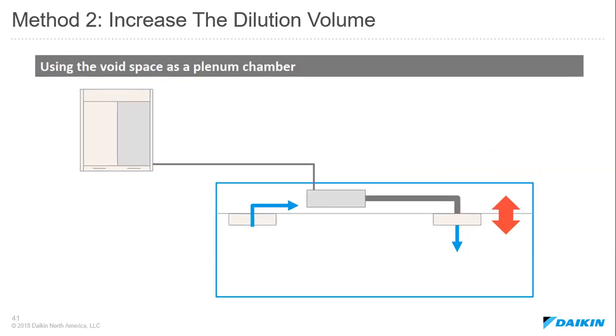Another thing we might do is use the void space as a plenum chamber where we're moving air. If we're moving return air through our plenum, that would allow us to count that plenum space in our dilution volume. And if we did that across the entire building, now all of those rooms become a singular space.